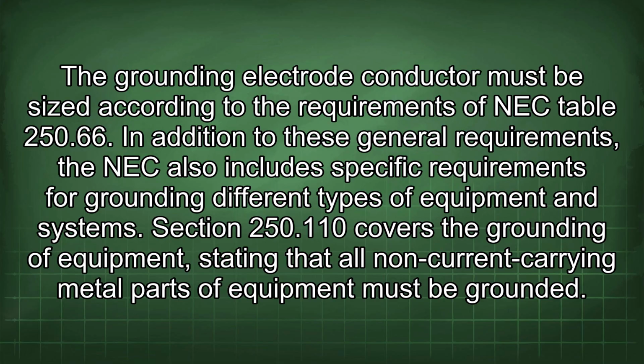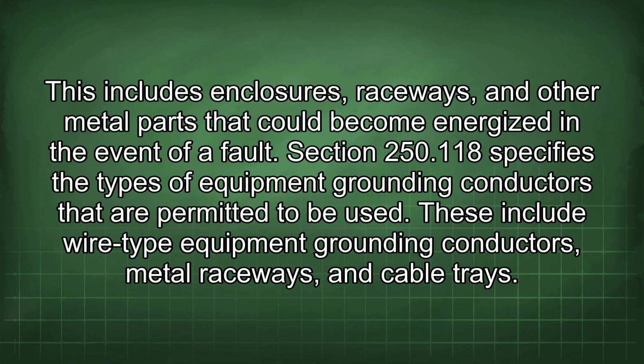Section 250.110 covers the grounding of equipment, stating that all non-current carrying metal parts of equipment must be grounded. This includes enclosures, raceways, and other metal parts that could become energized in the event of a fault. Section 250.118 specifies the types of equipment grounding conductors that are permitted to be used. These include wire-type equipment grounding conductors, metal raceways, and cable trays.